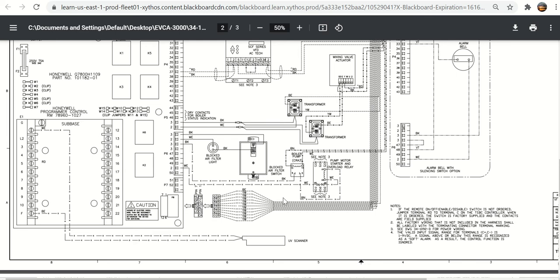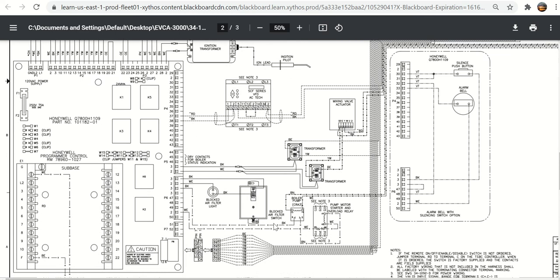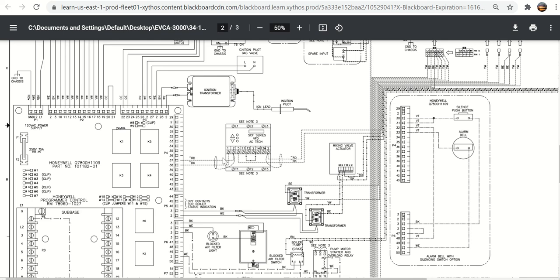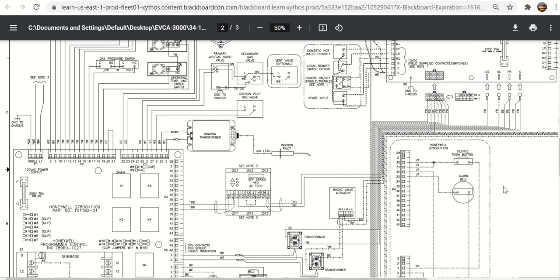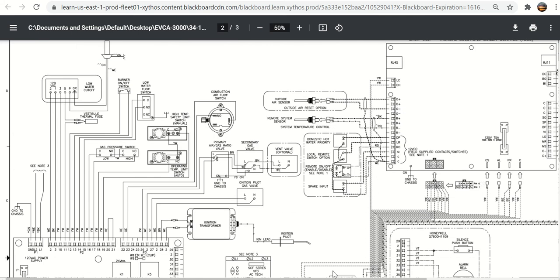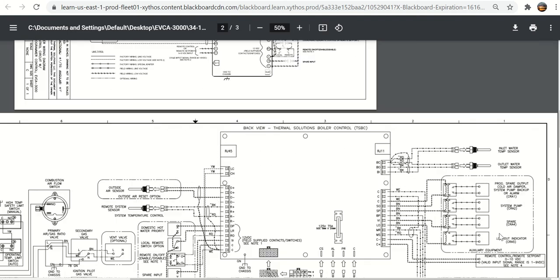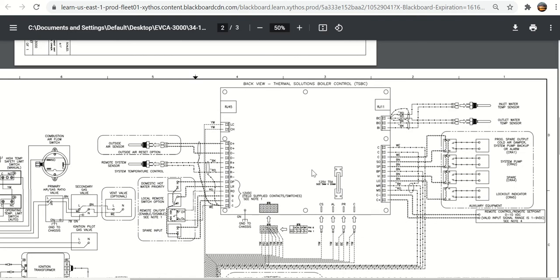Here are the terminals going out to communicate any type of a control status. Your blocked filter switch, 24 volt transformers. Here's the speed signal to the VFD. If you remember, there was a stop-start signal for the VFD, or maybe that is the stop-start signals for the VFD going in on 1 and 2 right there. And then here is the actual speed signal coming across from the TSBC controller. So let's move over here. That was pretty much the board that holds the flame safeguard on it.